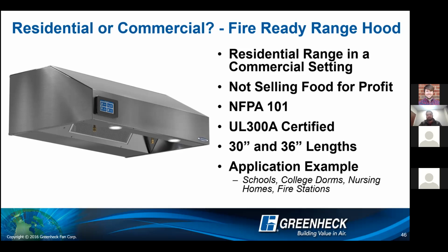Now, this can only be used over your standard residential ranges in a commercial setting that are either 30 inches wide or 36 inches wide. There's no overhang from the range. Those are the most common residential ranges on the market. And again, that's 30 or 36 inches wide. And then the question just becomes, do you need to have NFPA 101 for life safety? Where are you looking for these? So schools, college dorms, nursing homes is probably the most popular place that we see this.